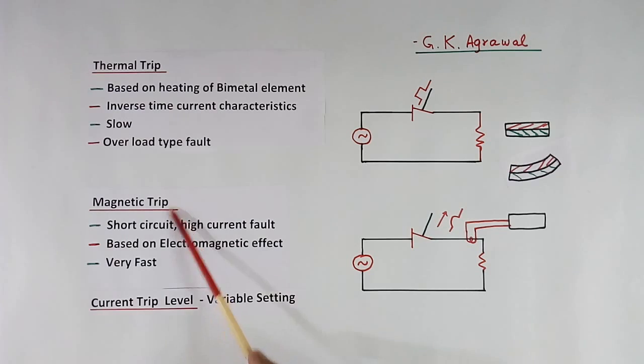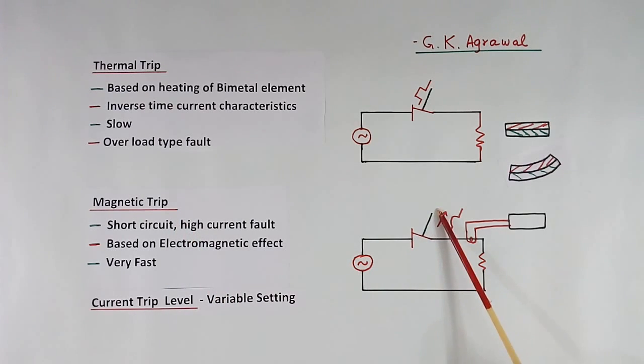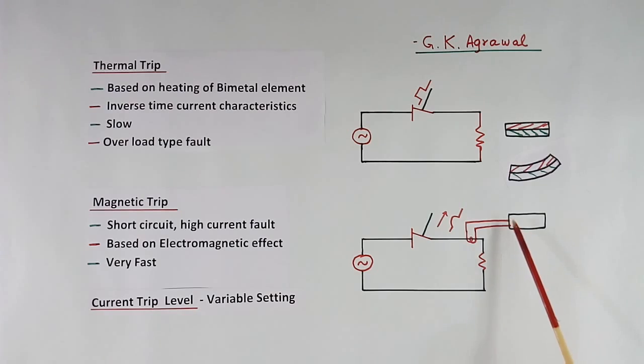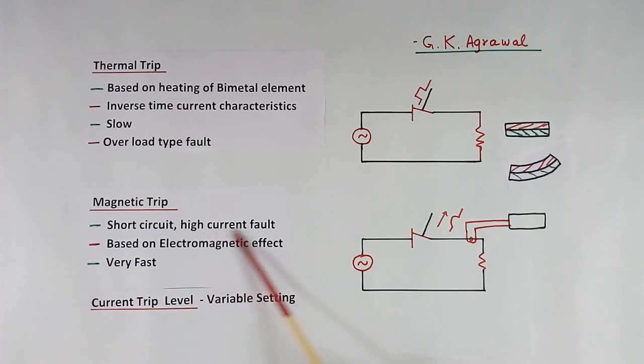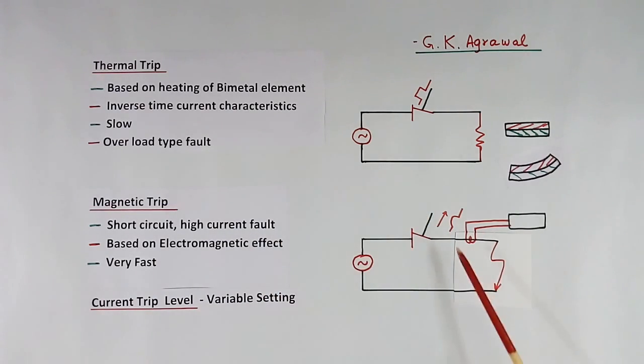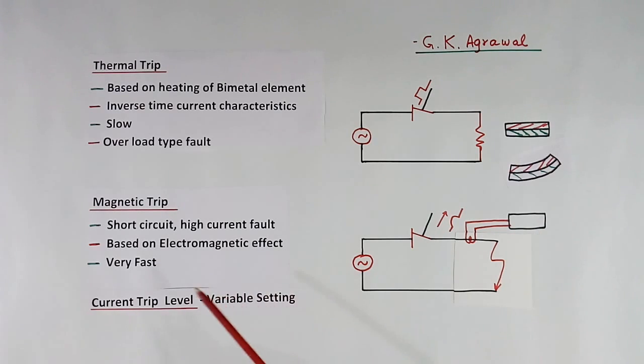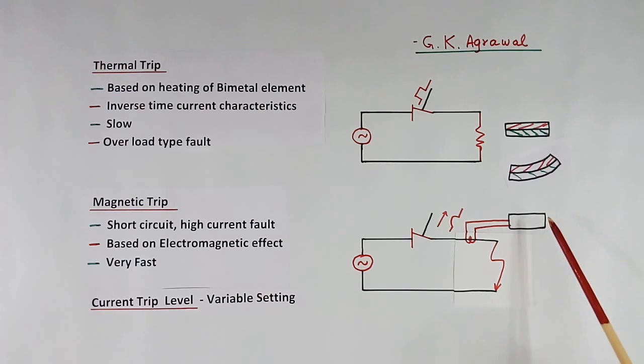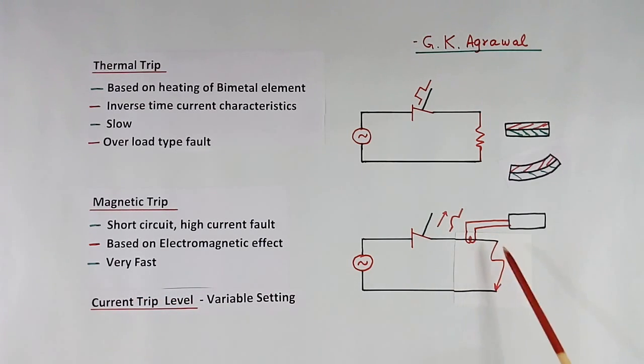Now magnetic trip. This is supply, this is the MCCB contact, and this is load. Here one CT is shown, which is part of the MCCB. This magnetic trip operates based on electromagnetic effect. Whenever a short circuit or high current comes, very heavy current will flow. The CT will send the current through a coil inside. Because of the electromagnetic effect of that coil, a magnetic material will get attracted, and because of the movement of that material, this contact will open. This is very fast — because heavy current will flow, immediately this coil will activate, and within a few milliseconds this breaker will trip.